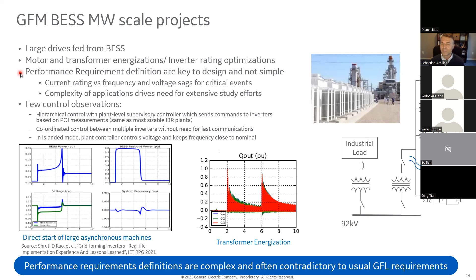One aspect of this project, though, just to close this, is that the performance requirements were extremely complex. In this case, the performance requirement was to have a battery system that can start this particular industrial system with this motor and that drive. So the definition of requirements in a more general way, trying to say, well, grid forming should have this and that feature, is actually more difficult than for this particular plant, because you have to generalize it. And also details in the requirements drive significant differences in the design of the system. So in particular in these battery systems, small details in the way we would be allowed to start motors will have a significant impact in the current rating we needed in the inverter-based resources. So performance requirements have a significant impact in the design for grid forming, and the requirements are not easy to define, as you know.